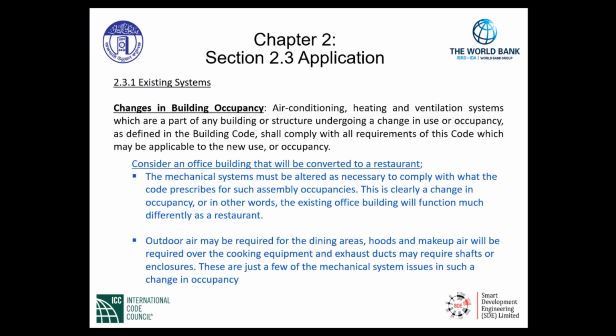Additionally, with a restaurant, we may have a commercial kitchen installed that needs exhaust systems, makeup air systems, and heating, cooling, and ventilation systems installed for that function within the new restaurant. Outdoor air may be required for the dining areas. Hoods and makeup air will be required over the cooking equipment. And exhaust ducts may require shafts or enclosures that must be compliant with the building code requirements. These are just a few of the mechanical system issues in such a change in occupancy.